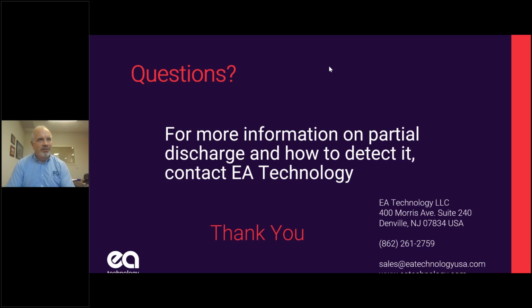It's just a very expensive, very time-consuming test, and there is some question over whether a 0.1 hertz or 0.01 hertz is representative of a 60 hertz situation. So that's where I strongly recommend test all your cables online at 60 hertz, and then do offline testing for the very small percentage that you actually detect PD on.